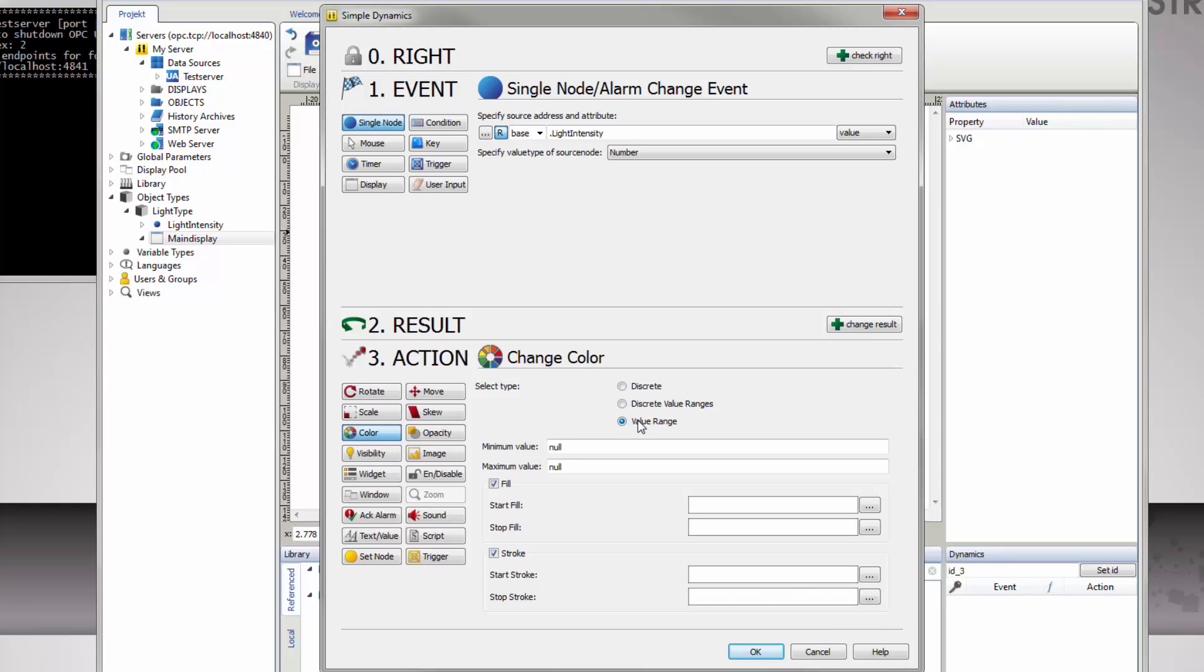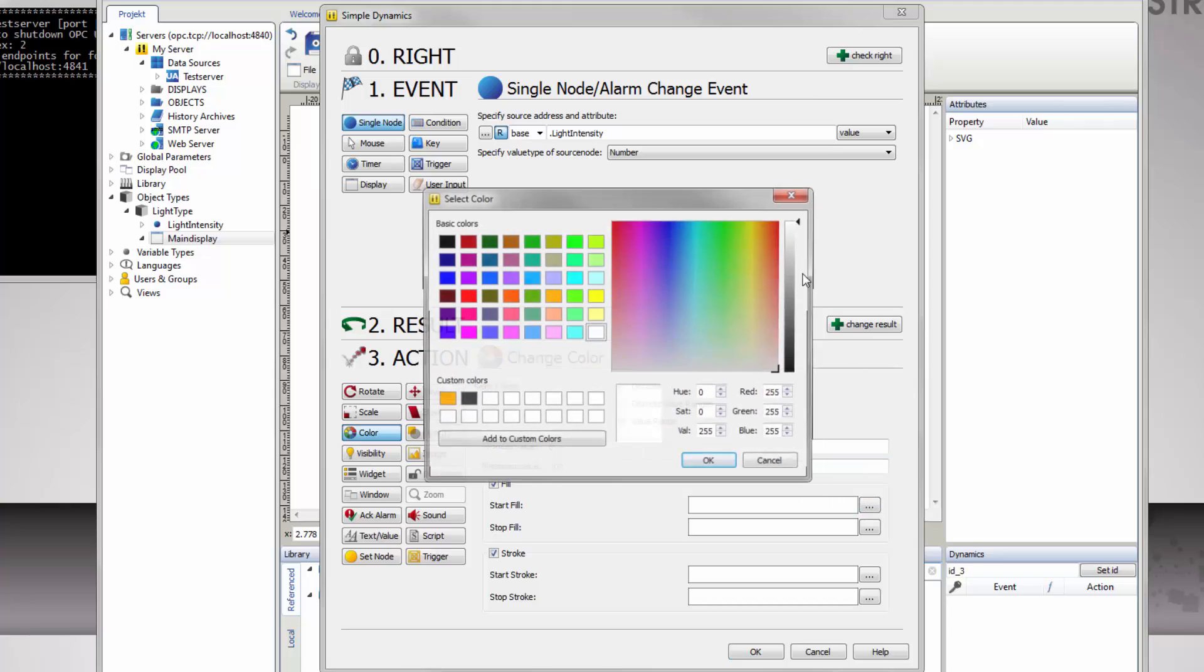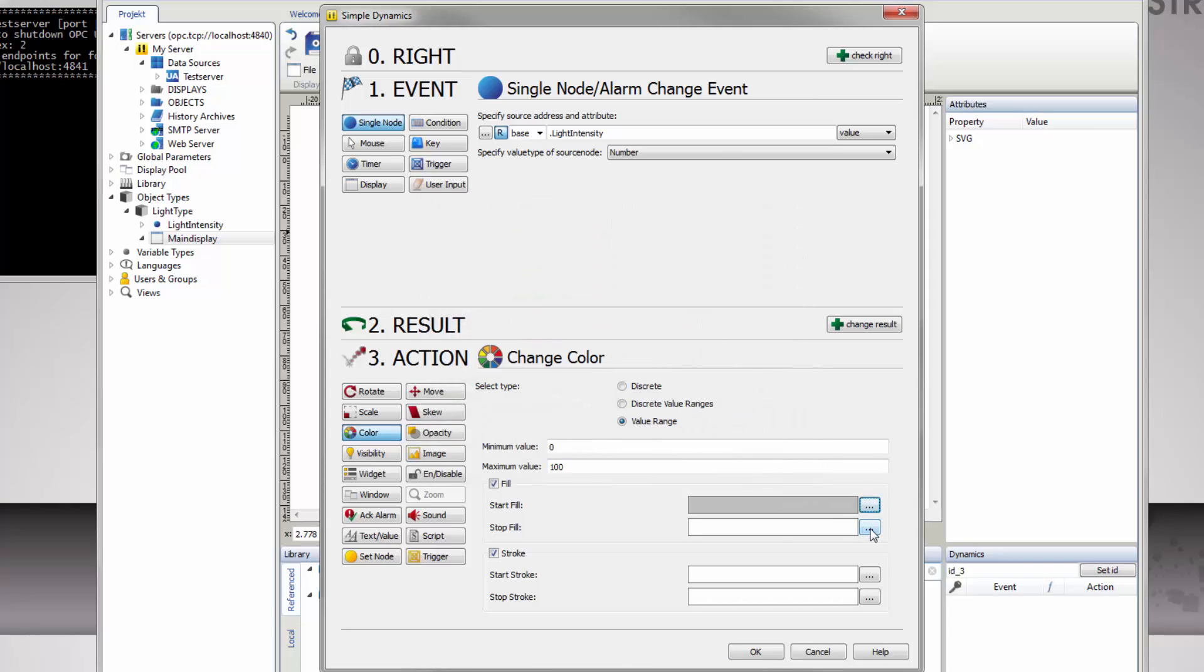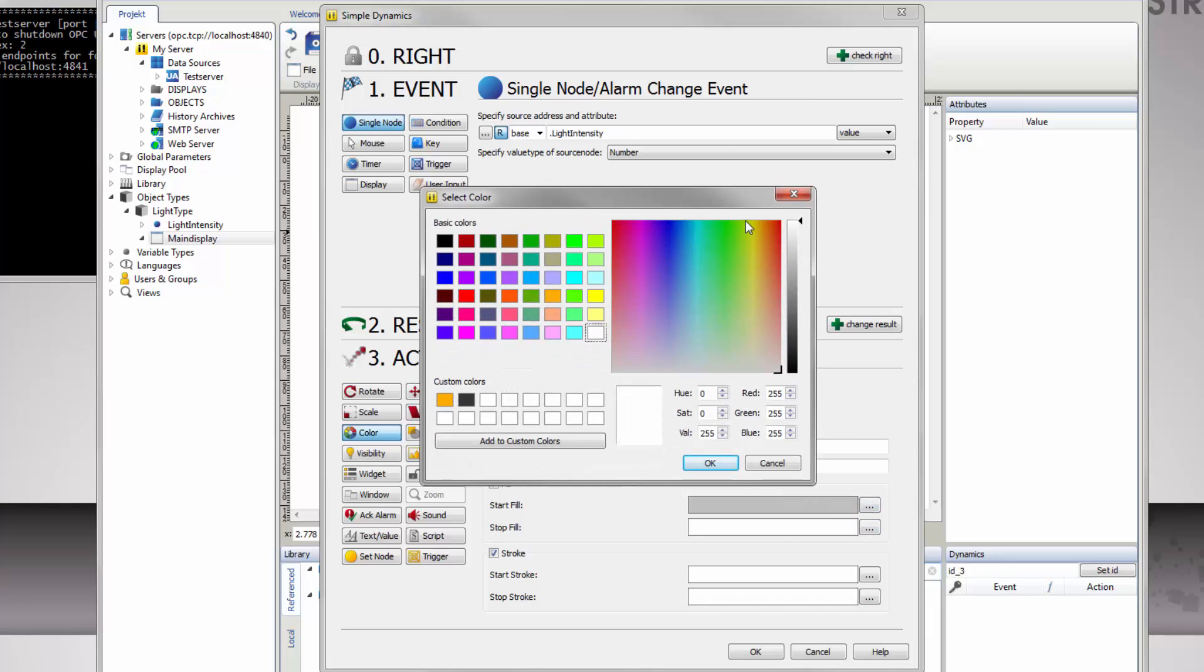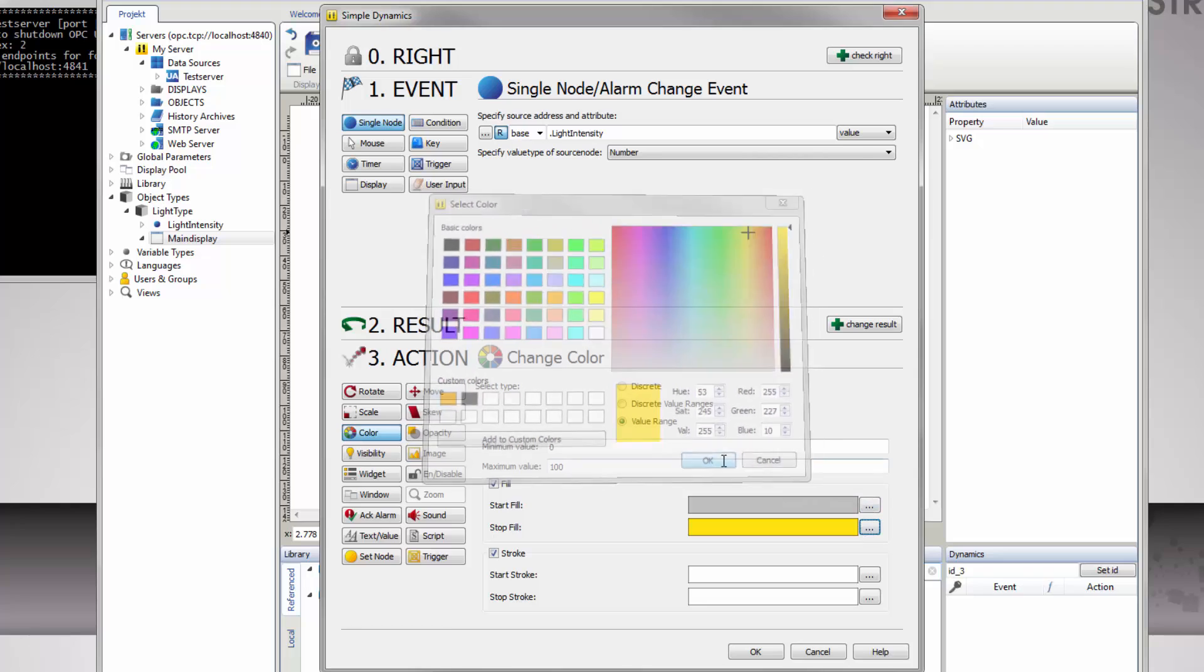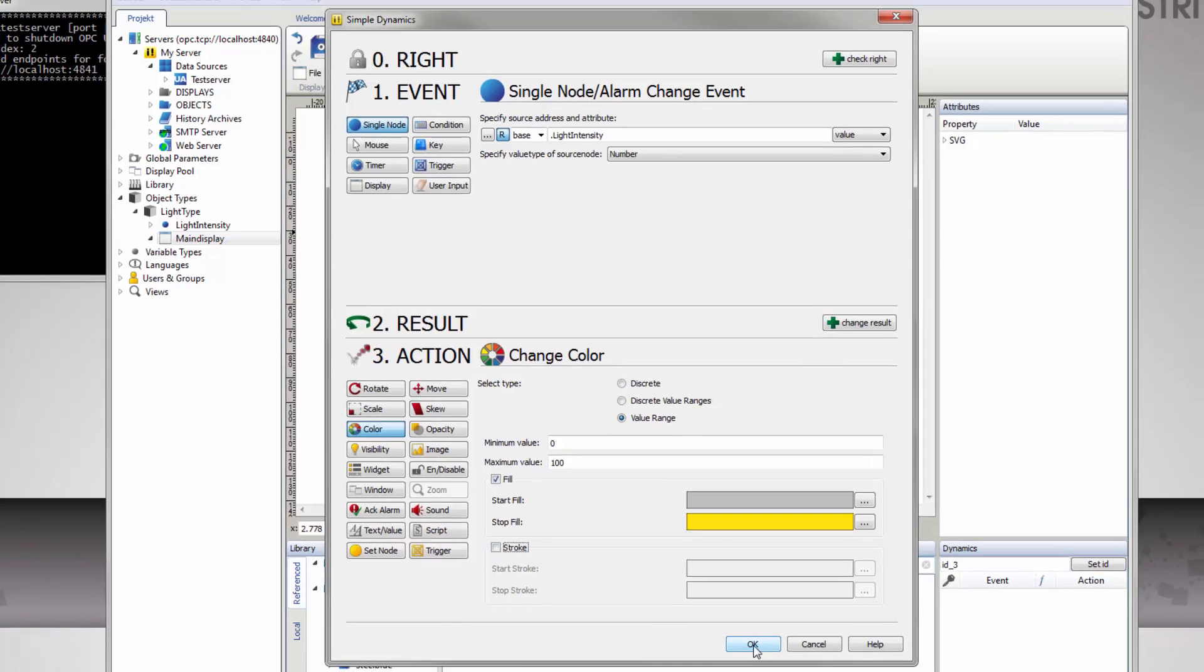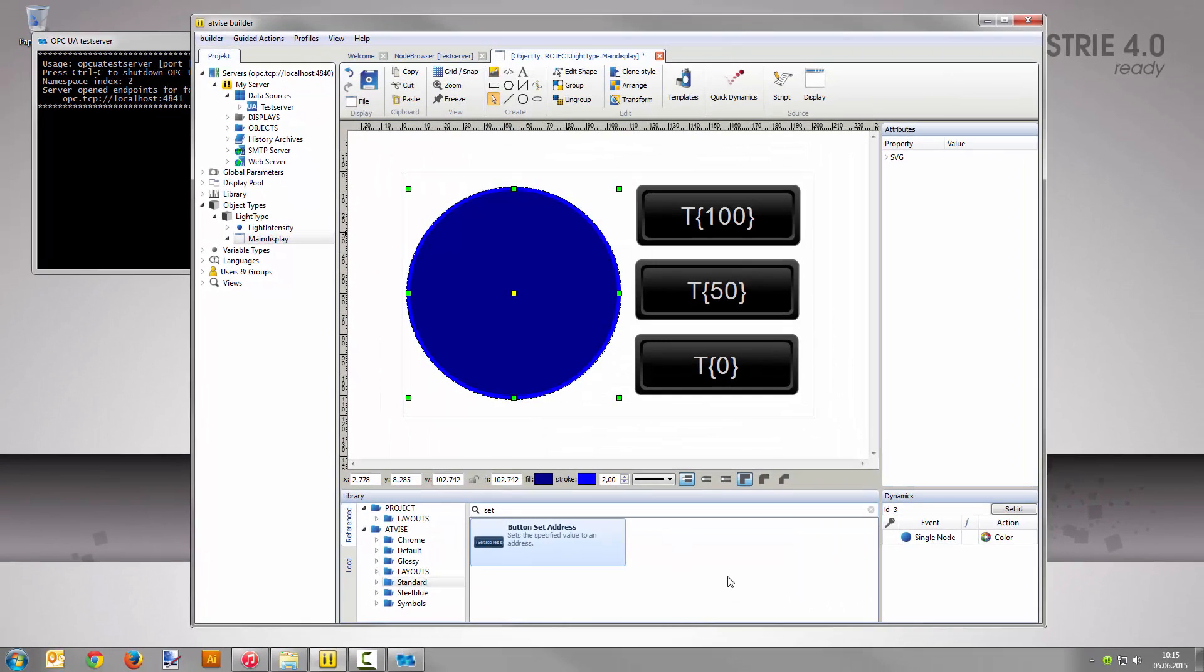Select color in the action area and value range as type. Set the minimum value to 0 and the maximum value to 100. As start fill color, choose a gray tone from the color palette, and a bright yellow as stop fill color. Remove the check for stroke because you only want to change the circle's fill color. Save the dynamization with a click on OK. Save the display in the graphic editor as well.